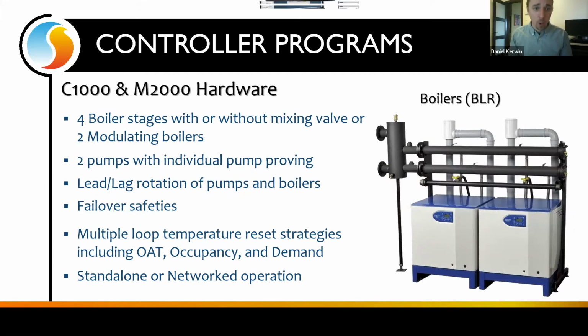We handle the loop pumps as well, and the boiler stages, as well as the system pumps. We have a lead-lag sequence in that we can rotate them after a specific amount of time. And we also have the failover safeties as well. So if we call one pump to turn on and then we don't have a proof or we don't have status, then the second pump will turn on. All of this is already built into this controller.